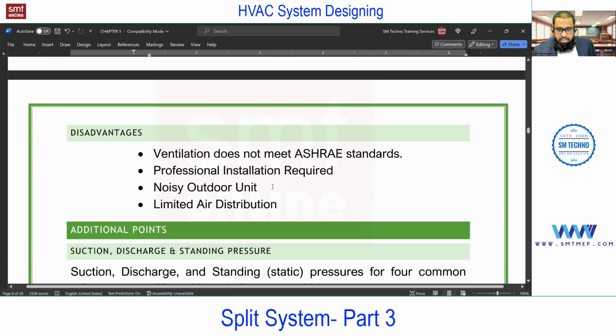Next, professional installation is required. Compared with the window unit, which is like plug and play, a split AC also needs an installation person, but here a professional is required so that after installation he can connect the copper pipes from indoor to outdoor with brazing, check the leakages between the pipes, and release the refrigerant from the compressor.